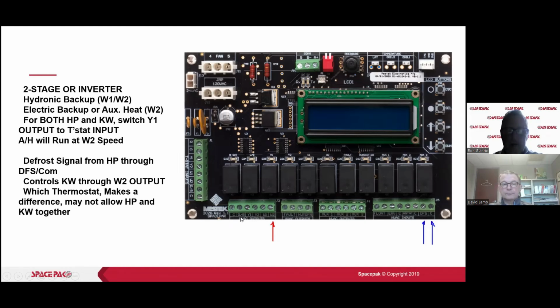There's no R down here. Okay, but we don't need an R down there because we're getting the 24-volt signal through Y1 and Y2. We've got a common right here, but we don't need an R down here if that's what he's asking, because we've got 24 volts through Y1. We've got a common for voltage return. We've got an OB, a Y2, and then a W1, W2 here as well.